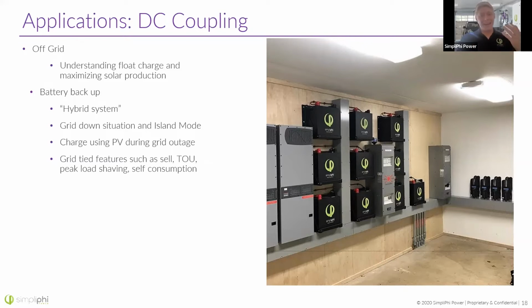When you look at an AC coupled grid tied system, that power is all on one bus. So your AC coupled PV array and your AC power coming from the grid, it's all on one bus. So it's hard to separate what power is coming from where. The best you can kind of do is disconnect from the grid during those time of use hours when power is expensive. It's hard to say, oh, I'm only going to sell to grid when power is expensive, because who's to say you can't have power flowing both ways in that situation?